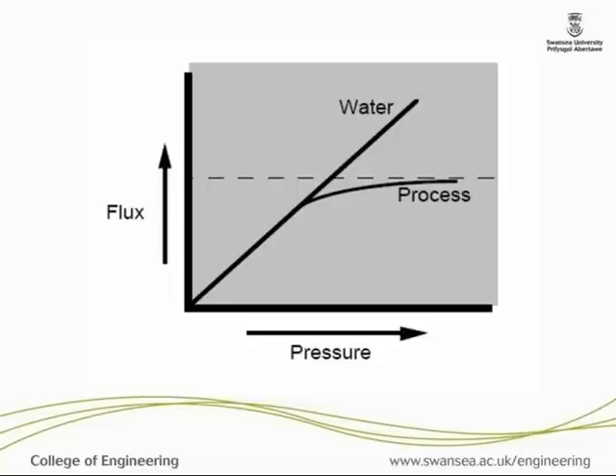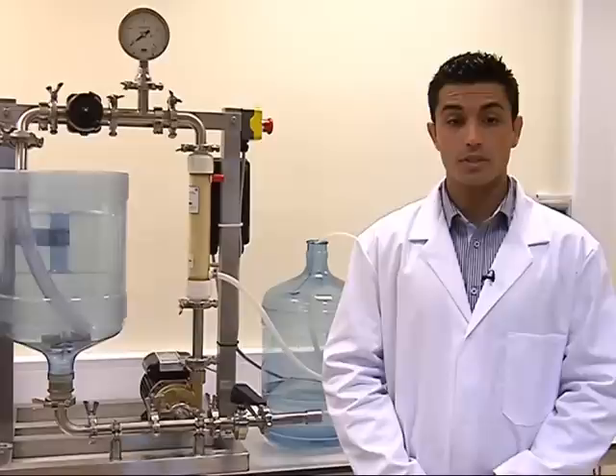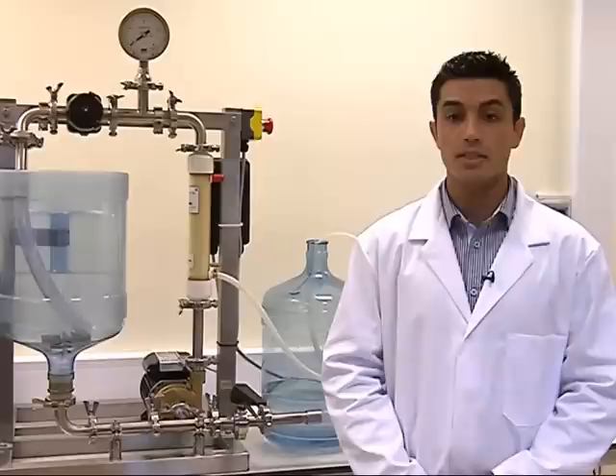Thirdly, probably the most important parameter in filtration is pressure — transmembrane pressure. Pressure drives the fluid around and out of the system. Even though higher pressures result in high flux, this is not linear after a certain level. There is also a transmembrane pressure allowance specific to every membrane unit and type. Most importantly, the absolute pressure on the membrane outlet can never be the same as the pressure at the inlet, otherwise there won't be any flow. These considerations are paramount for the establishment of an optimal filtration process, which minimizes the loss of flux due to membrane fouling.